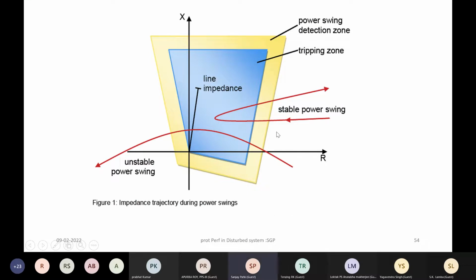So this is typically the picture on the impedance side. What we see here is the typical picture on the impedance side. Again, this is an R-X diagram, and for 400 kV lines it is recommended that the characteristic chosen for the distance relay should be a polygonal characteristic. Why a polygonal characteristic is chosen is basically because the reactance reach, which is basically the line impedance, is independent of the resistive reach of the distance relay. These can be set independently.